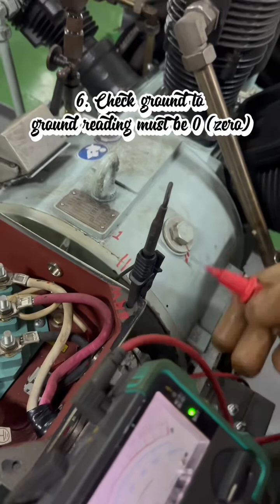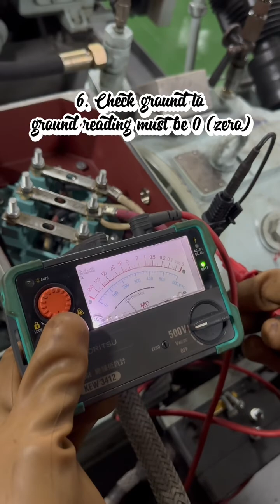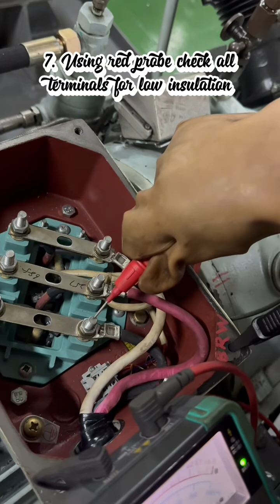And check the ground to ground. Reading must be 0 mega ohms. And lastly, using the red probe, check all the terminals for low insulation.